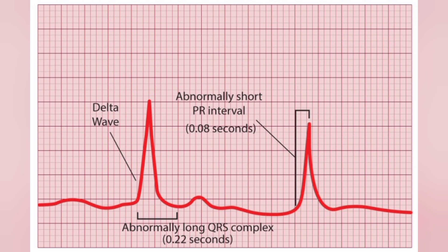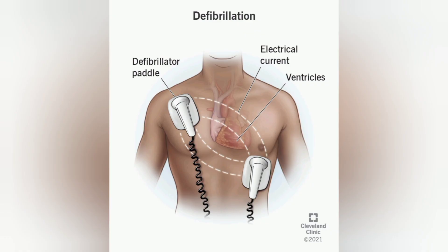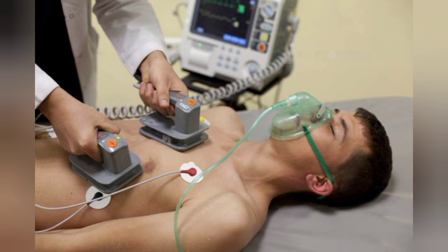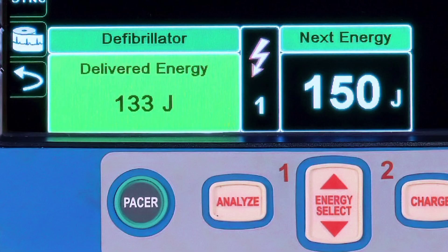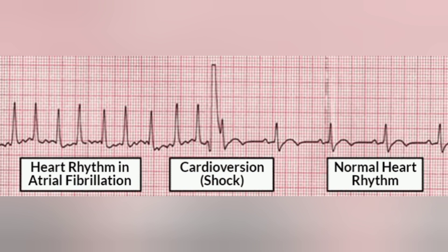All these syndromes create an abnormal or faulty ECG pattern. A defibrillator consists of two metal pads and ECG lead wires. When the ECG cable is connected to the patient's chest, it produces an ECG signal and displays it on the device screen. The device detects any fault in the pattern of ECG. This device is operated on a patient only by doctors or a trained clinical team. As the defibrillator detects the problem, it indicates to give a shock to the patient. Doctors set an appropriate energy level and attach the pads on the patient's chest, which delivers the shock. This process is done until the patient's heart is beating in rhythm.